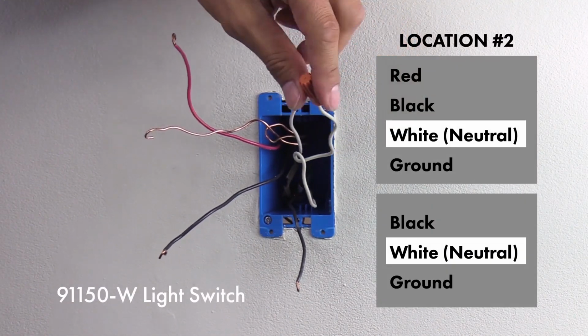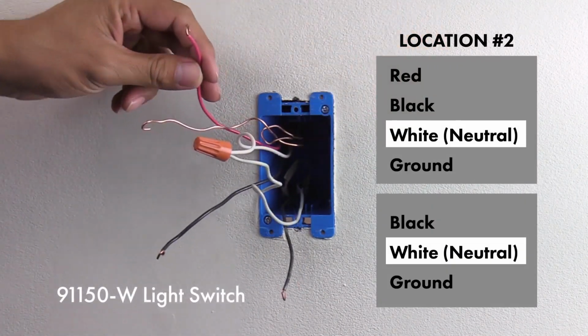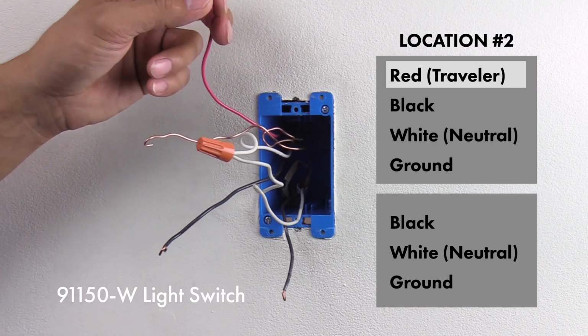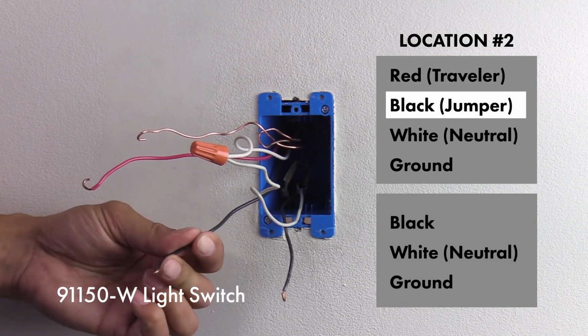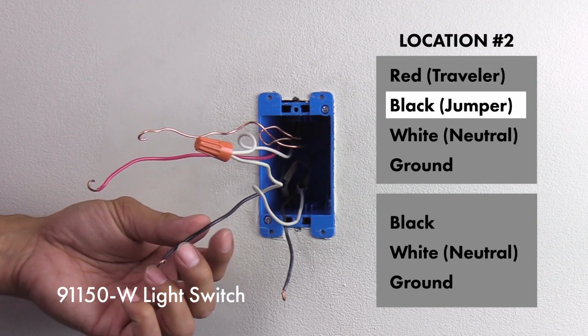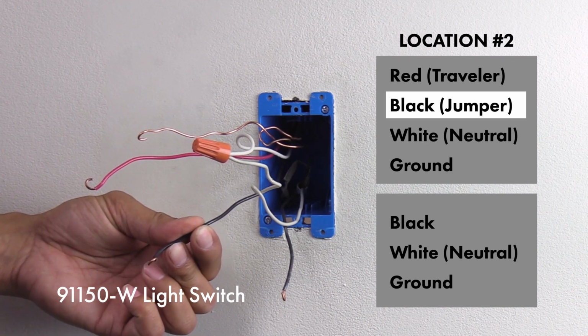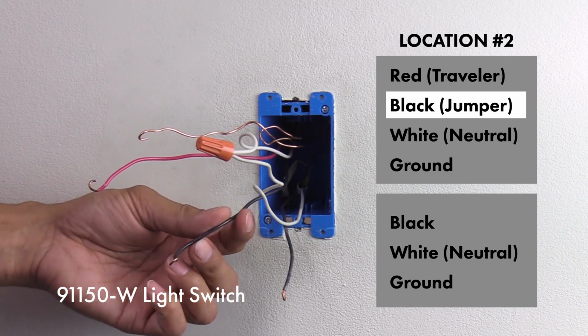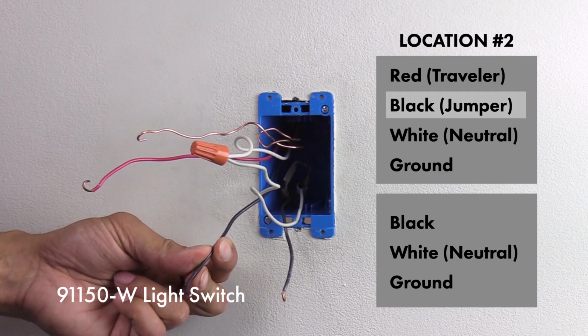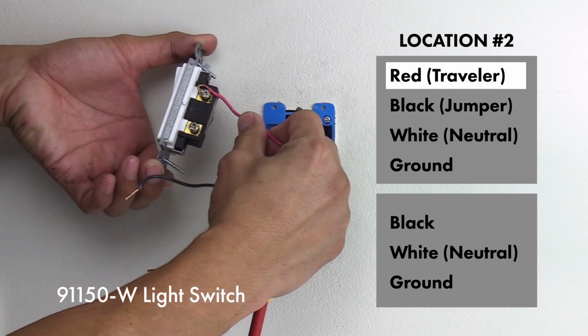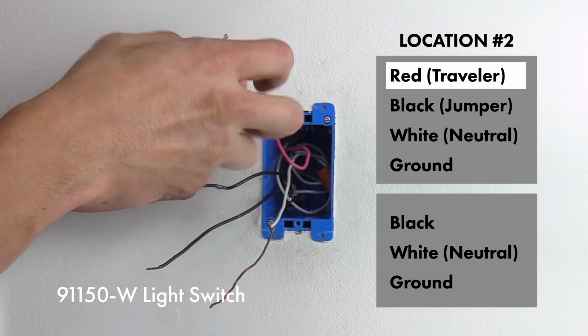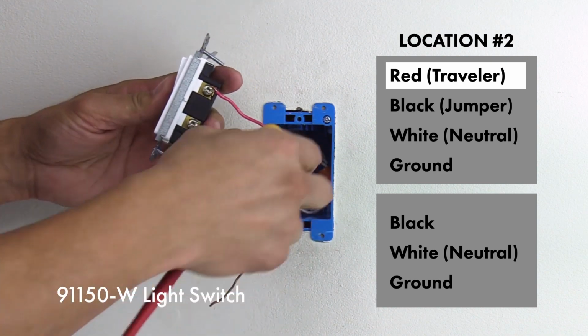The white wires are your neutral wires. The red wire will be your traveler wire. The black wire coming from the same set of wires with the red wire will be used as the jumper to relocate the hot input to the other switch location. Connect the red wire to the other terminal on the 91150 switch.